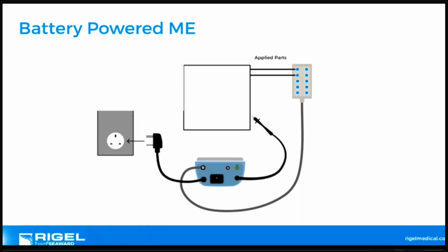But fundamentally, the way that you should do any testing for battery powered devices, if it's purely battery powered, is this: because of the capacity of the battery, you don't know what inverters are in these things to produce the amount of power. It could have a really high capacity battery in there. But really what the guidance says and how we do our testing, 62353, you can test it, applied parts testing.